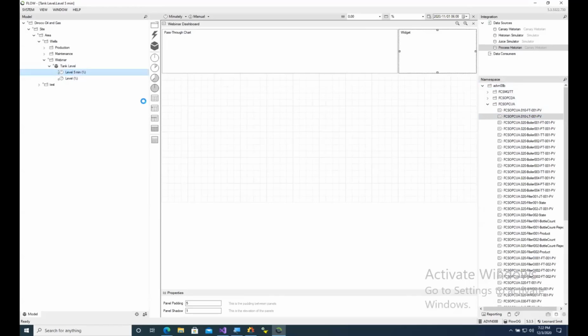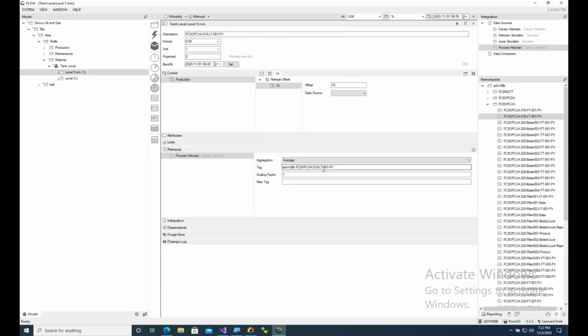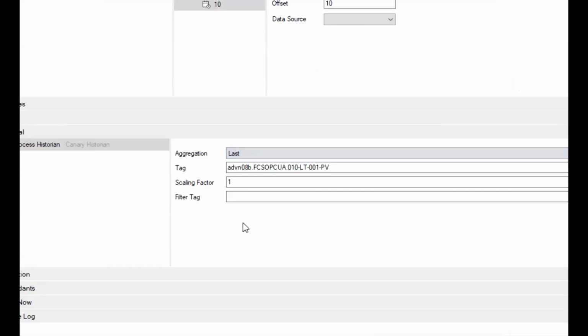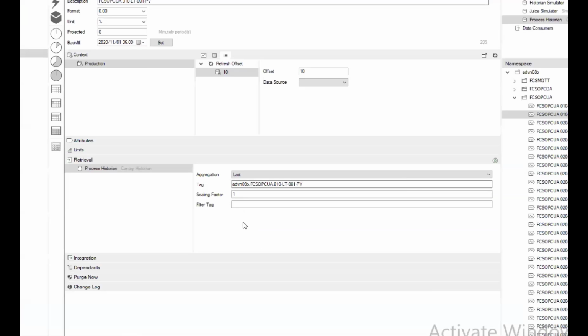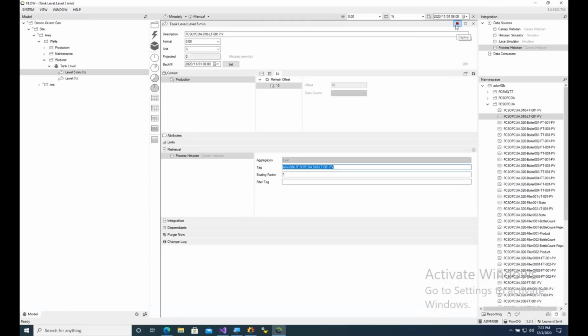Again, I'm going to look at the last value of every 5 minutes because that is going to give me the better resolution of what the last value for that 5 minute time period is. Perfect. I'm going to deploy that out. And now what I can actually do, when it's done going through all the historical data, doing the backfilling and giving me the actual result, is marry this 5 minutely value to my historical hourly widget, which is very cool. Sorry, it's just running through, getting all of the data and backfilling through my historian. And there we go. Cool.